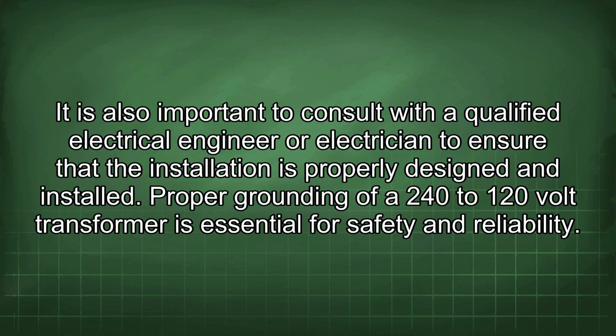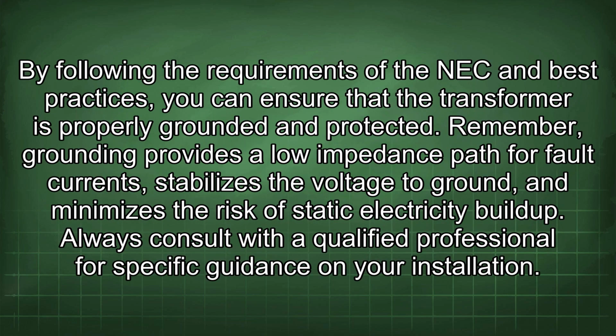Proper grounding of a 240 to 120 volt transformer is essential for safety and reliability. By following the requirements of the NEC and best practices, you can ensure that the transformer is properly grounded and protected. Remember, grounding provides a low impedance path for fault currents, stabilizes the voltage to ground, and minimizes the risk of static electricity buildup. Always consult with a qualified professional for specific guidance on your installation.